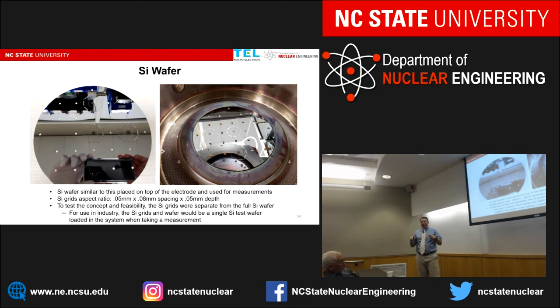And as a single wafer, you could put that in your system, maybe every 50 or every 100 wafers that you're running, to just make sure your ion energy measurement is the same. So you put it in, the robot would take it, slip it in, set it down, and then you could take an ion energy measurement after every 100, every 200 wafers you run. And so basically that grid allows access to the drift cones, or to that surface mount probe.